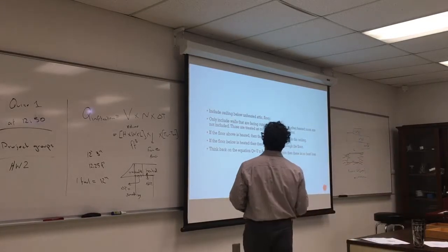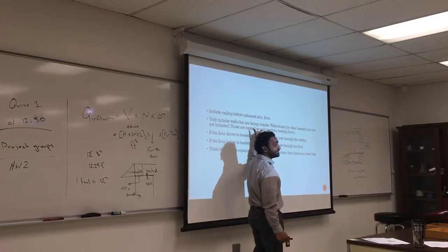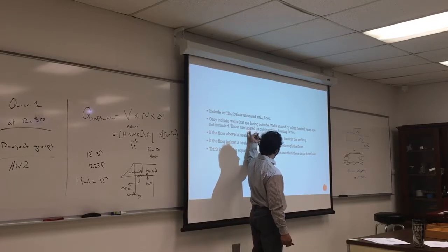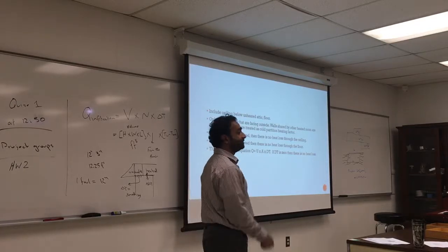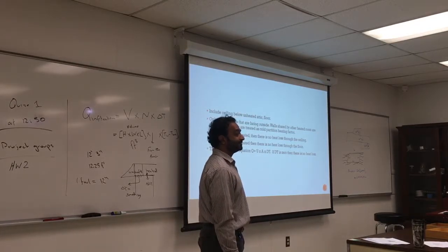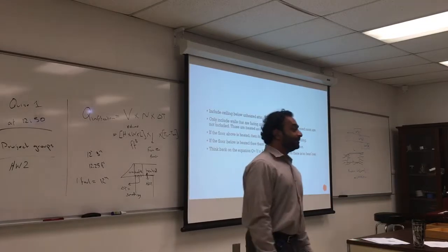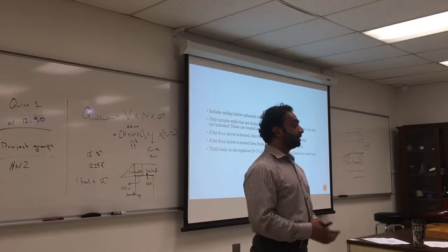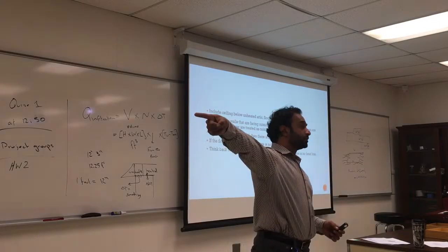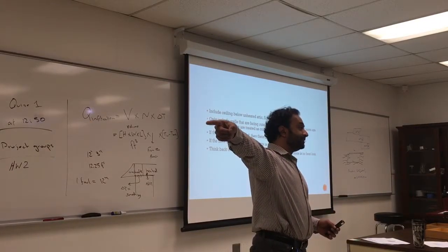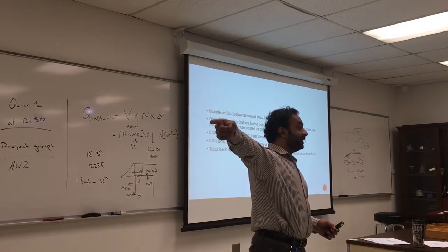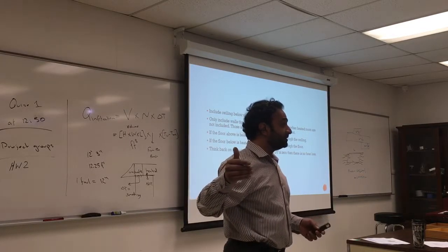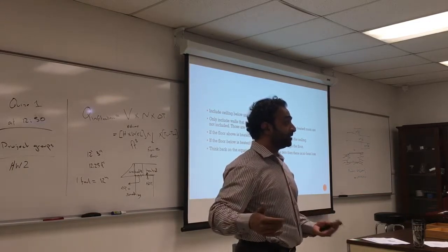Only include walls that are facing the outside. I hope this is registering by now. Walls shared by other heated rooms are not included. Why? Well, if I want to do the heat loss from this room, I'm not going to include this wall because it's an inside wall. It's not touching the outside. The temperature is probably the same as here, so there's not a lot of heat transfer.